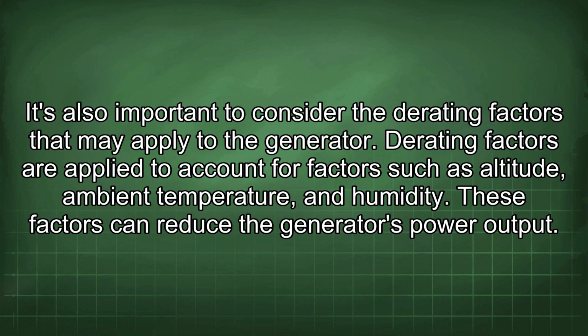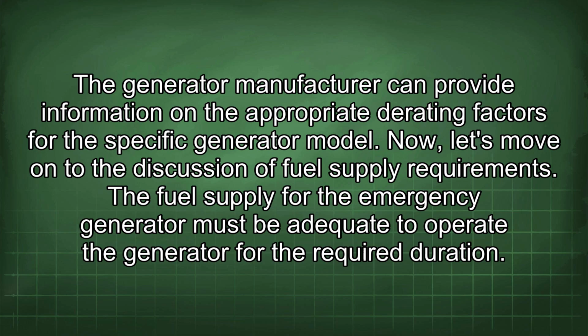Derating factors are applied to account for factors such as altitude, ambient temperature, and humidity. These factors can reduce the generator's power output. The generator manufacturer can provide information on the appropriate derating factors for the specific generator model. Now let's move on to the discussion of fuel supply requirements.